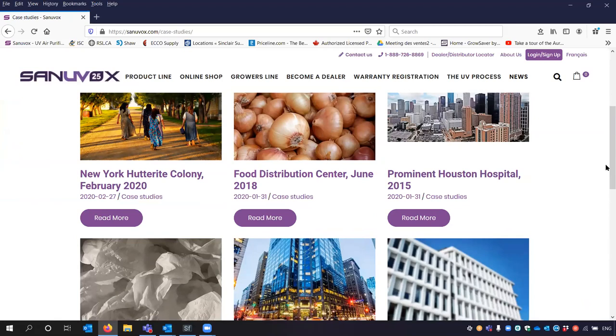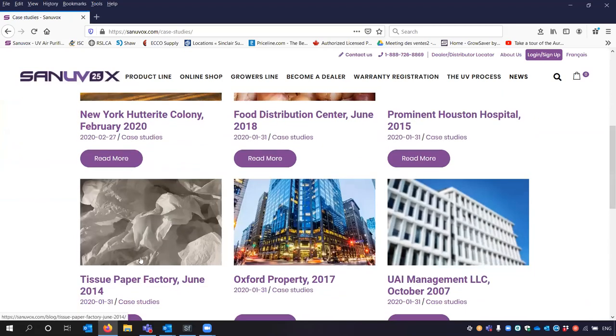As I was saying with coil cleaning, there's a case study here of a toilet paper manufacturing facility. With bacterial biofilm on the coils, their big wall of coils would plug solid from the fibers of the toilet paper they were manufacturing. They didn't believe us that it was a bacterial biofilm issue, so when we were allowed to treat the first couple of coils, they immediately saw the benefit of the coils staying clean. Where the UV was, it was clean as a whistle; where it wasn't, it was plugged solid. We ended up doing the whole facility.